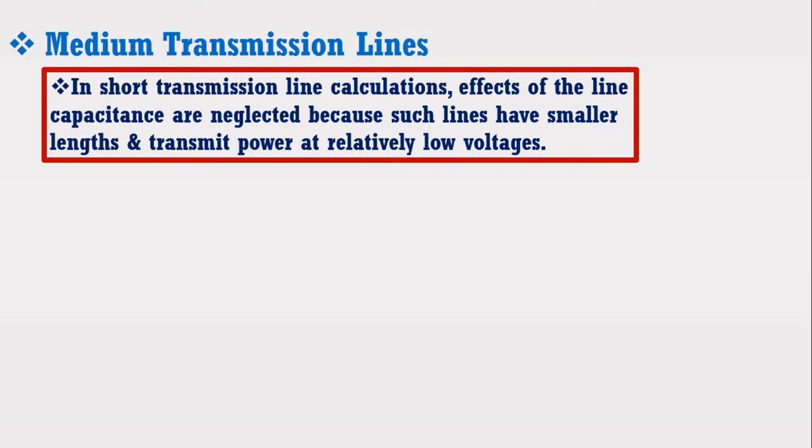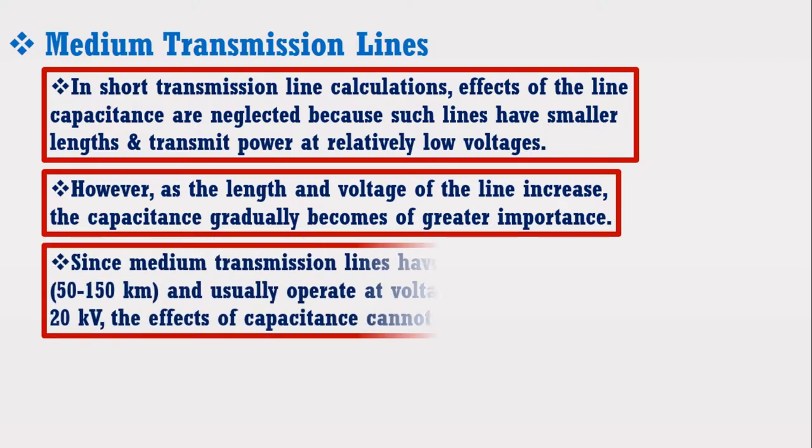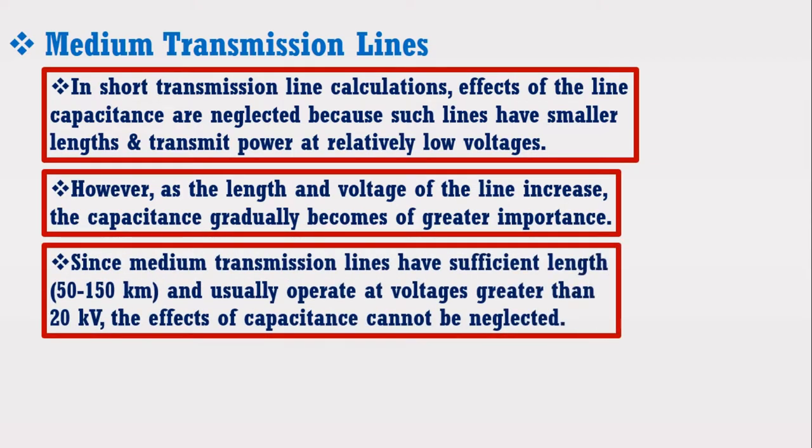However, as the length and voltage of the line increases, the capacitance gradually becomes of greater importance. Since medium transmission lines have sufficient length of almost 50 to 150 km and usually operate at voltage greater than 20 kV, therefore the effects of capacitance cannot be neglected.